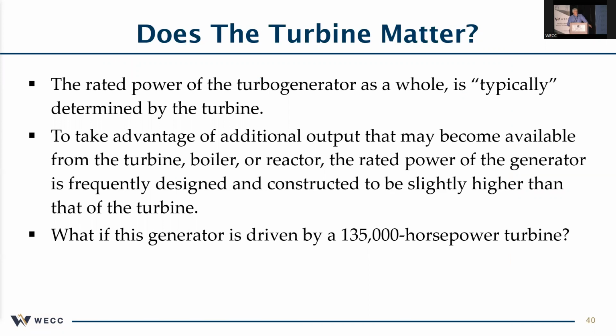In this case, this is from a discussion about generators. Normally when they make a turbine and generator set, it is typical to make the generator slightly higher capacity. You can overfire boilers, and there are some upgrades you can put on to possibly get a little more power out of the generator, but you don't get more power out of the prime mover. So the generator usually has a little margin in it, so you're not limited by that. So what if the generator from this previous nameplate has a 135,000 horsepower turbine on it? And that happens to be actually true in this case.